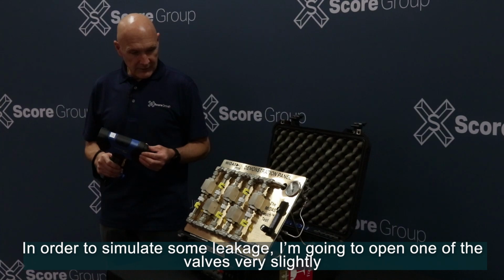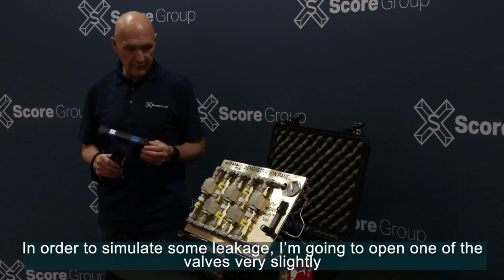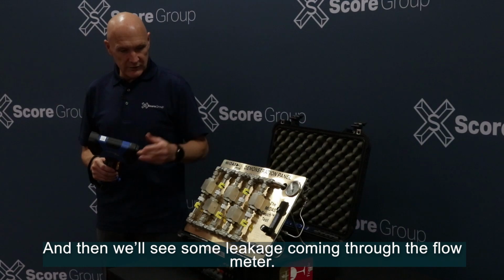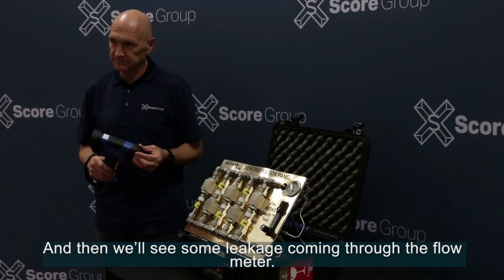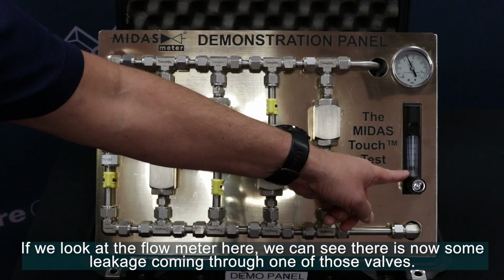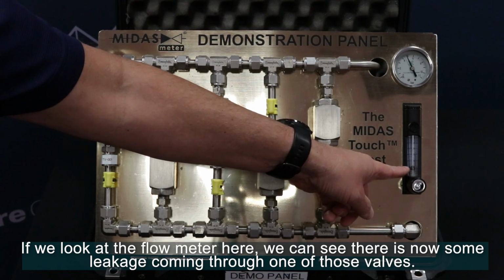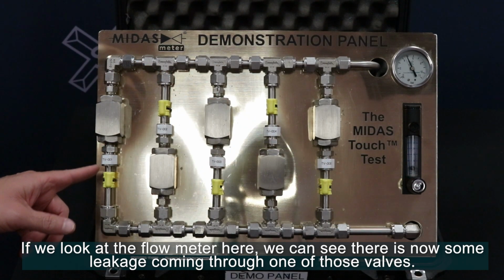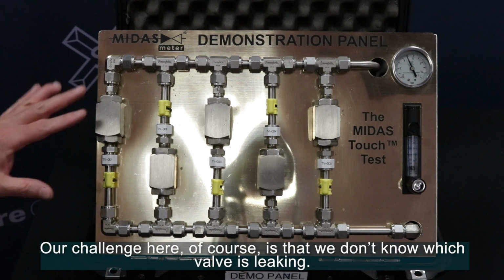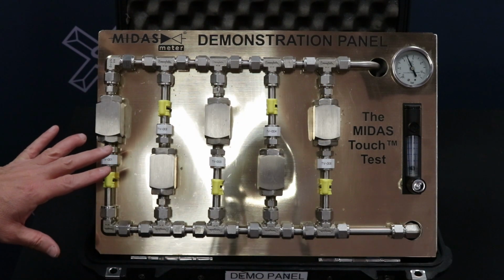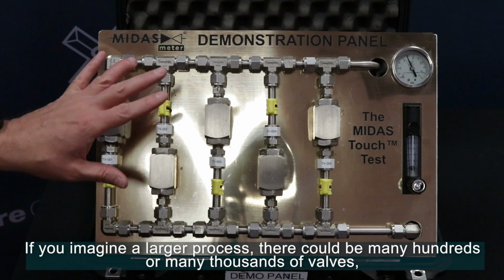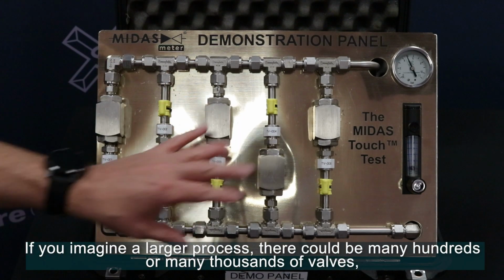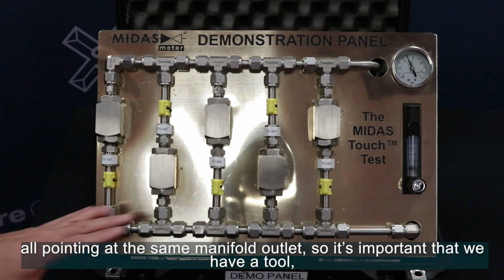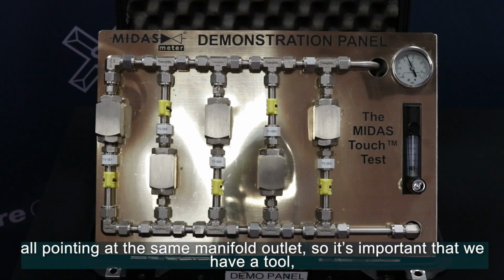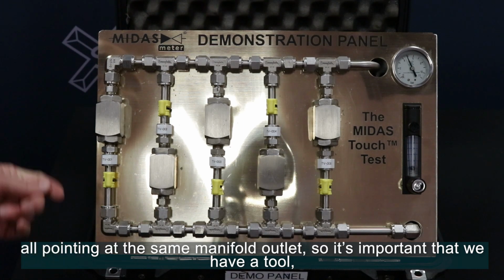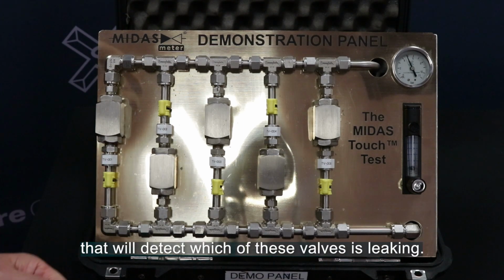In order to simulate some leakage, I'm going to open one of the valves very slightly, and then we'll see some leakage coming through the flow meter. So if we look at the flow meter here, you can see there is now some leakage coming through one of those valves. Our challenge here, of course, is that we don't know which valve is leaking. If you imagine a larger process, there could be many hundreds or many thousands of valves, all pointing at the same manifold outlet. So it's important that we have a tool that will detect which of these valves is leaking.